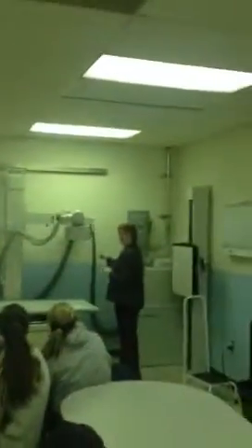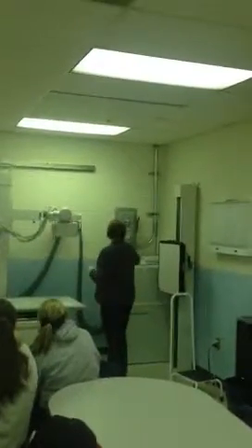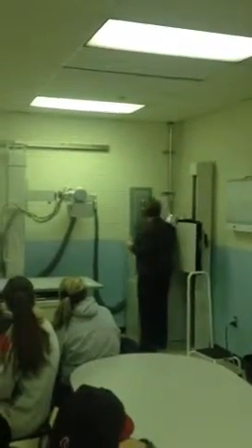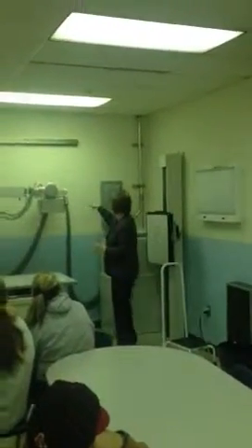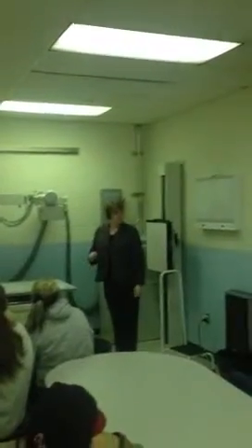All right, so 7 feet upward from the floor, and so this wall barrier would be a what? Secondary. And it's going to overlap the primary, kind of like wrapping paper. We're going to fold it over right here by how much? Half an inch. How much lead is in that wall? 1/32 inch, which is half of 1/16.